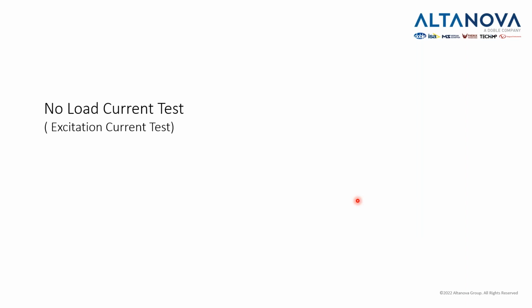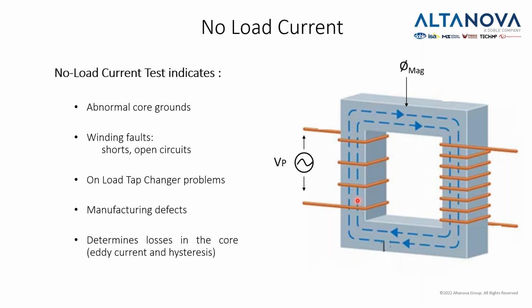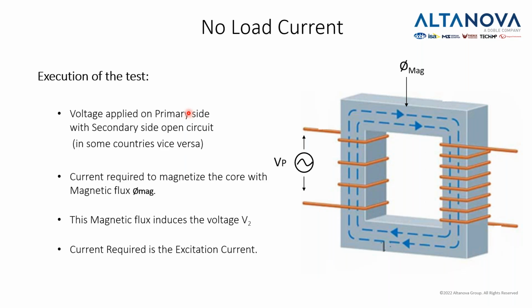The next test we're going to talk about is the no-load test or excitation current test. It's one of the tests that allow us to find out the parameters of our transformer. So this test will show us the losses in the core. Basically, what we need to do is generate voltage on the primary side with the secondary side open. That's the only thing we need to do. This test will show us abnormal core grounds, winding faults, on-load tap changer problems, and manufacturing defects as well. And as I said, determine the losses in the core.